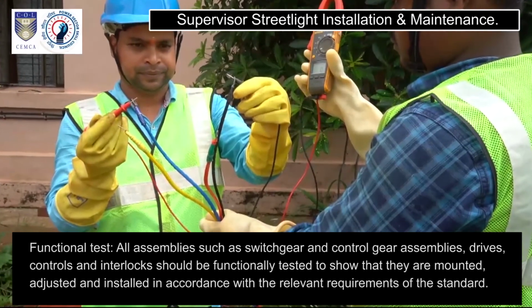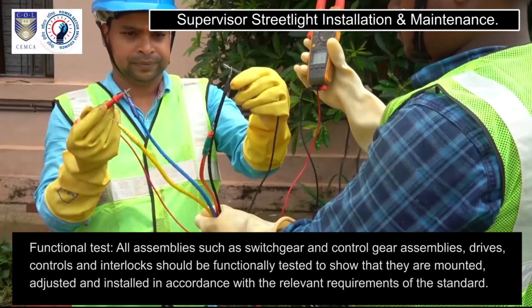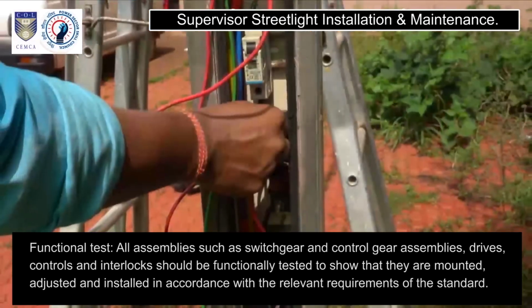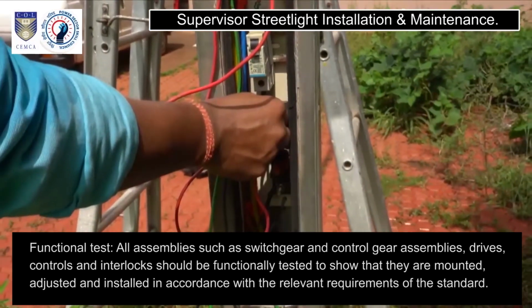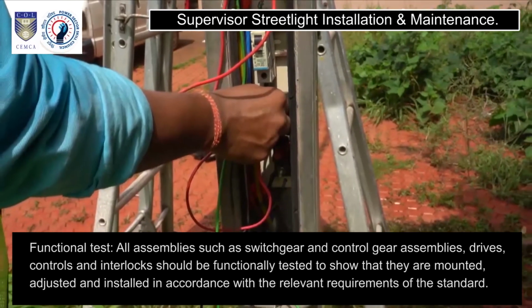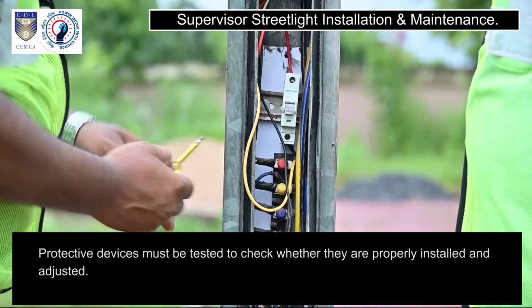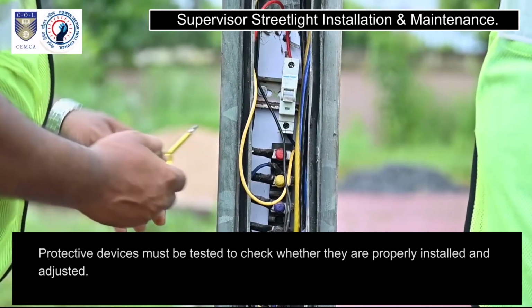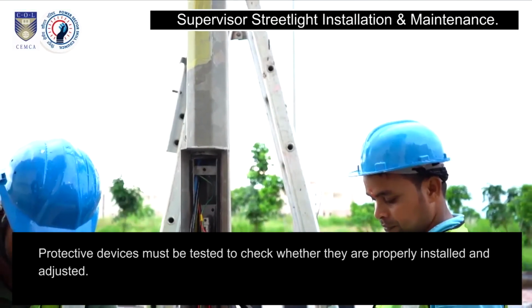Functional test. All assemblies such as switchgear and control gear assemblies, drives, controls and interlocks should be functionally tested to show that they are mounted, adjusted and installed in accordance with the relevant requirements of the standard. Protective devices must be tested to check whether they are properly installed and adjusted.